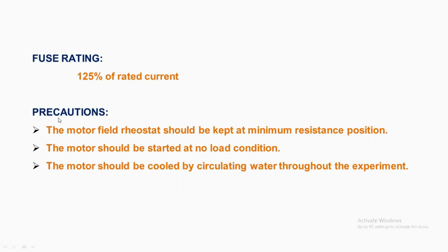Before starting the motor, you should consider some precautions. The 3 precautions are: the motor field rheostat should be kept at minimum resistance position. Then the motor should be started at no load condition. Then third, the motor should be cooled by circulating water throughout the experiment. These are the 3 important precautions before starting the motor.